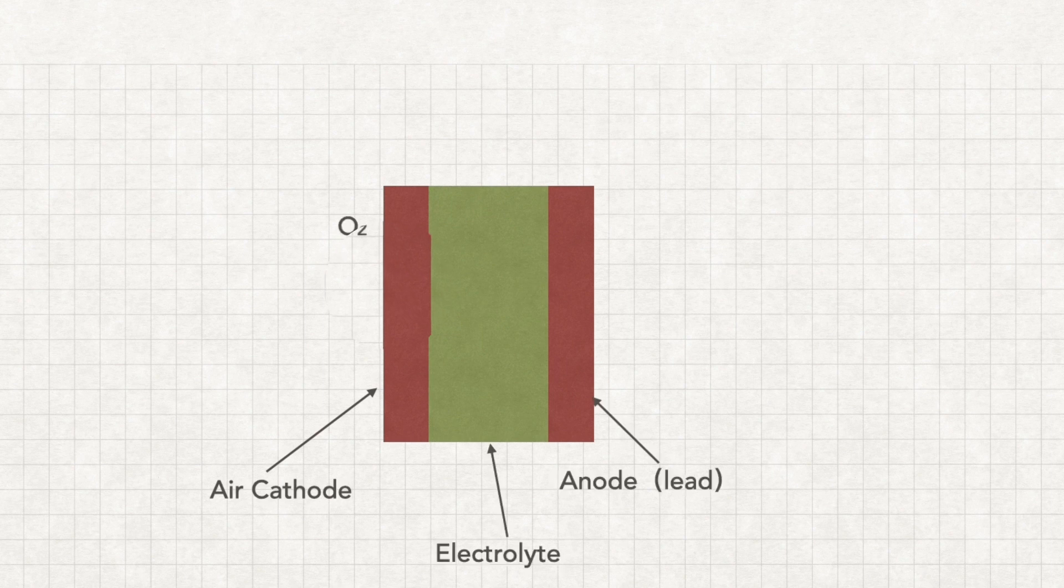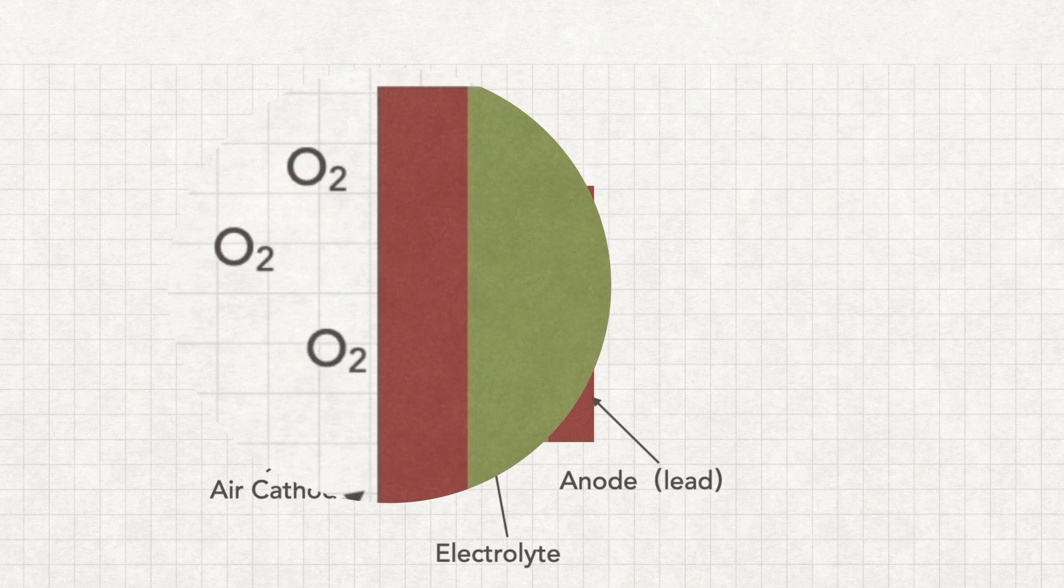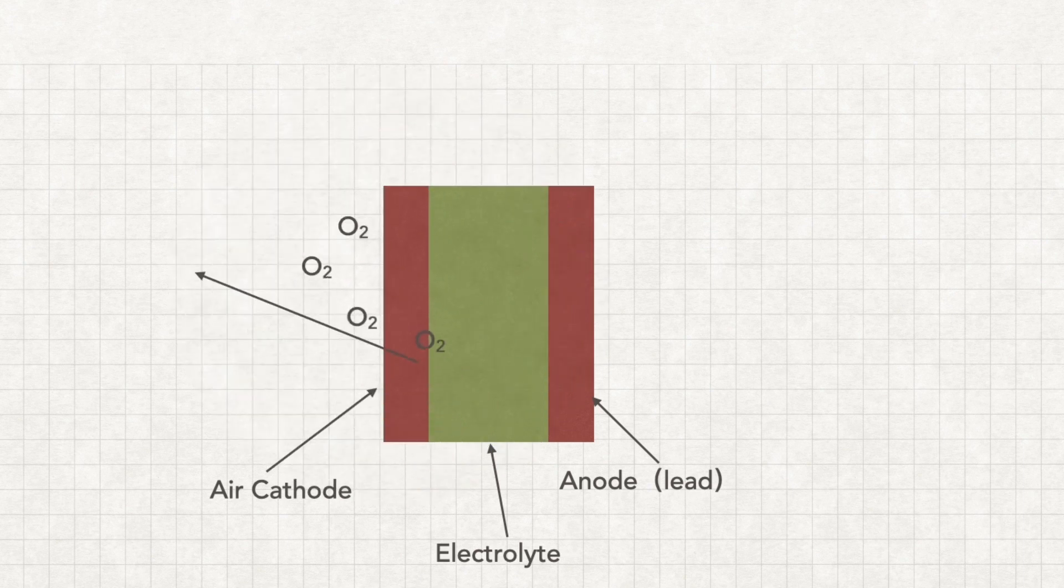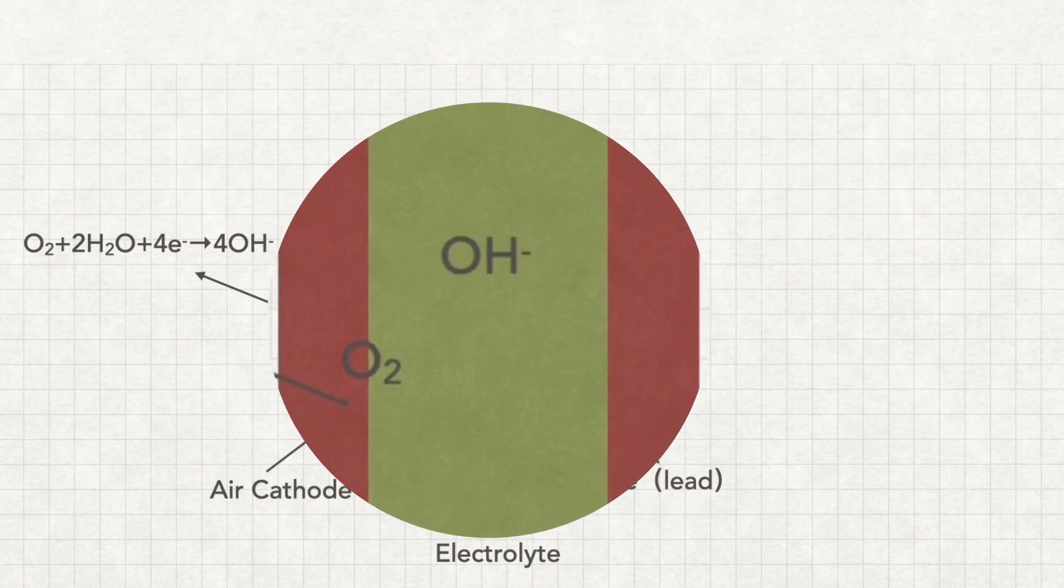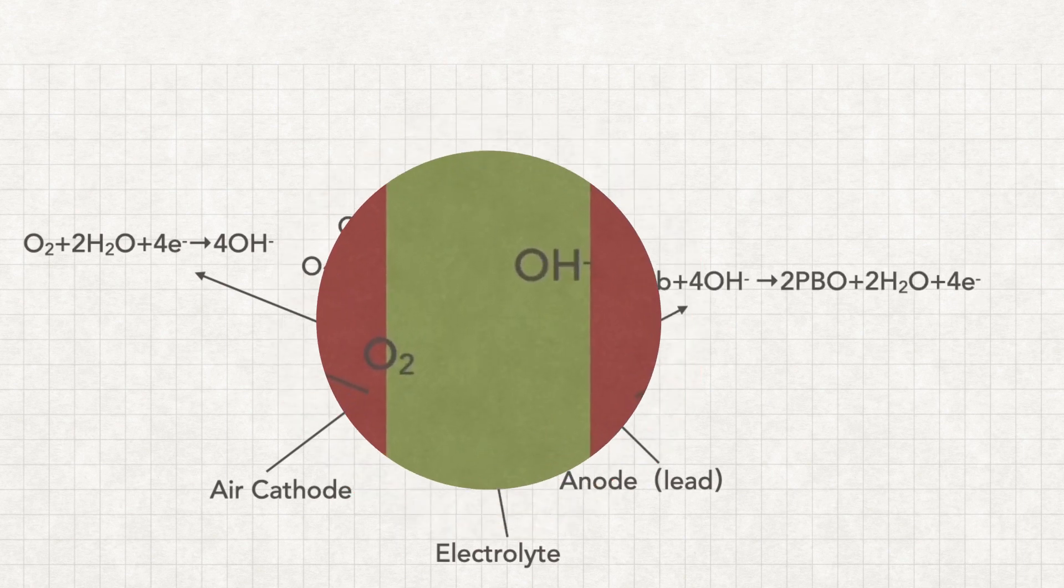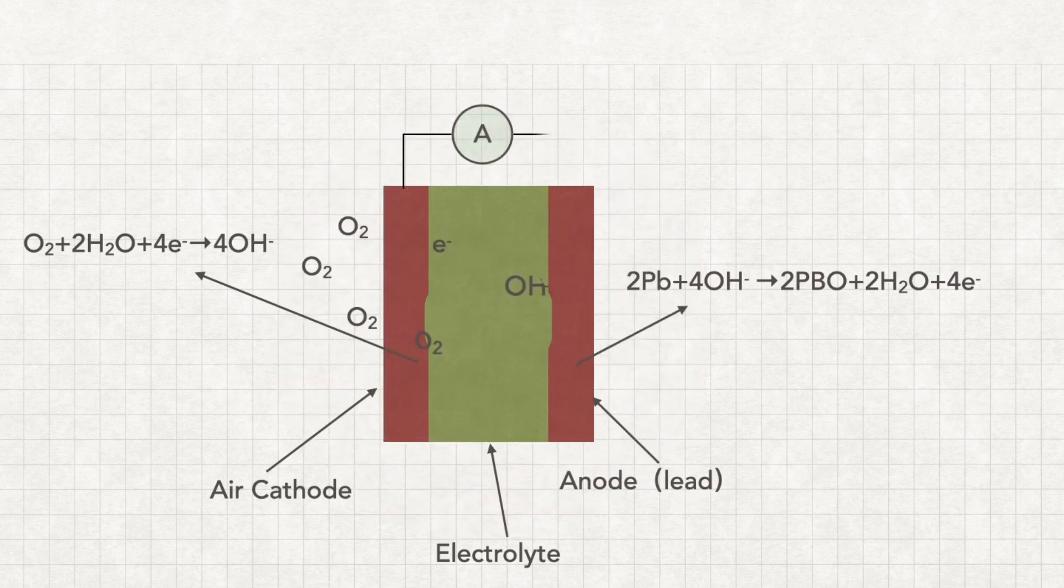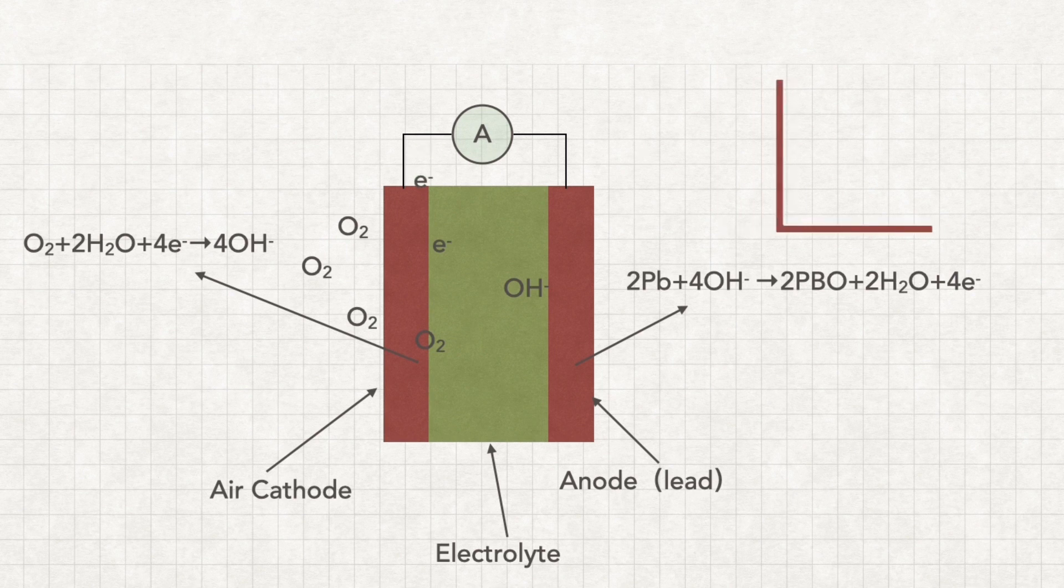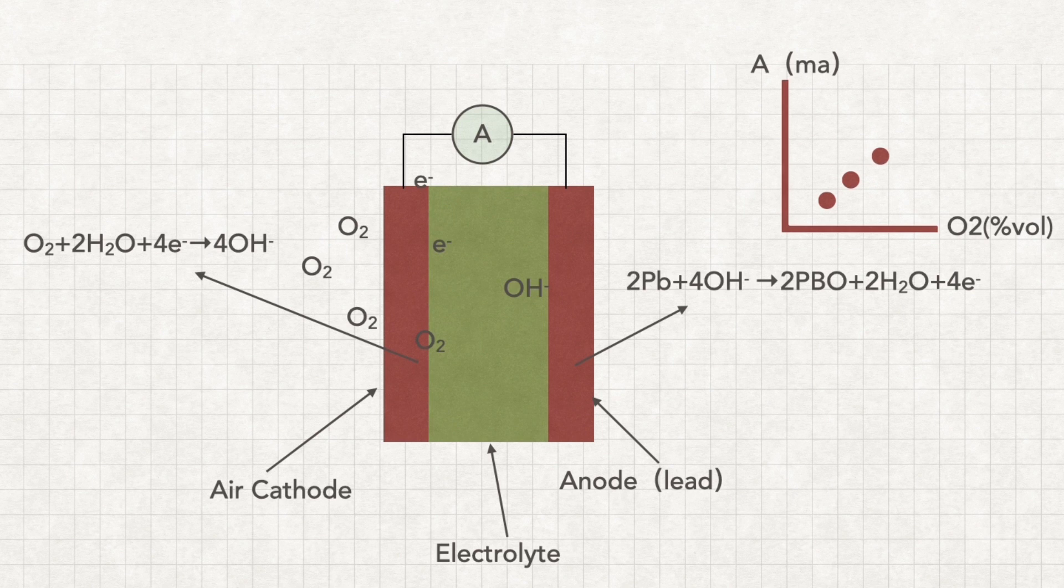When oxygen reaches the working electrode, it is immediately reduced to release hydroxide ions. These hydroxide ions pass through the electrolyte to the lead anode, where they undergo an oxidation reaction to produce metal oxide. These two reactions generate an electric current, the magnitude of which depends on the oxygen reaction rate. The current magnitude is proportional to the oxygen concentration. Thus, we get the value of the oxygen content.